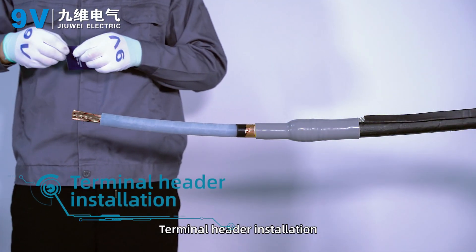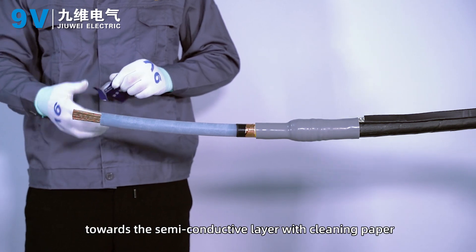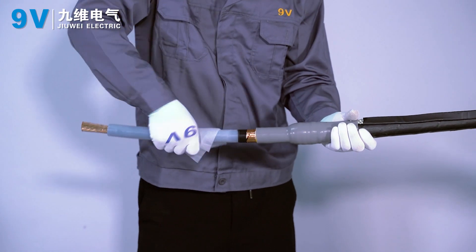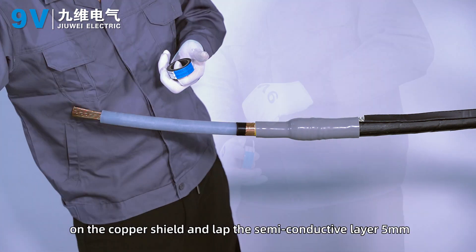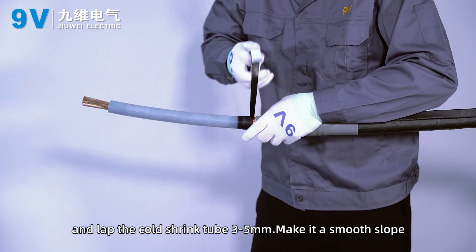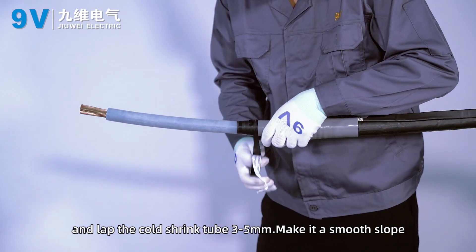Terminal header installation. Clean the surface of the insulating layer towards the semi-conductive layer with cleaning paper. Wrap semi-conductive tape in semi-lap mode on the copper shield, lapping the semi-conductive layer by 5 mm and the cold shrink tube by 3 to 5 mm, forming a smooth slope.